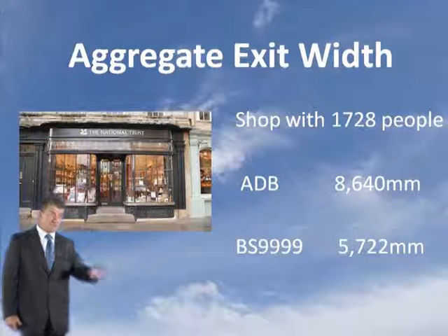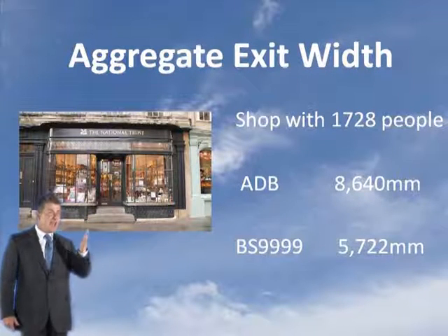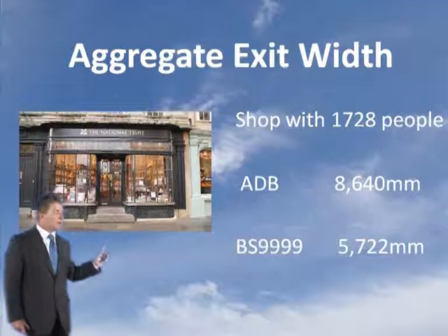BS 9999, especially if it's sprinklered, with early warning, high ceilings, etc., you can get it down to 5722. Is BS 9999 just for larger developments? No. Any shop out there, especially sprinklered, you want to look at this code. It's a B2 risk profile. You want to look at this code because it's going to design a much better design for your client. Much better design. What about the stair widths then?